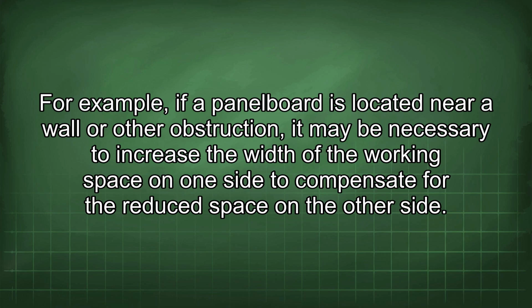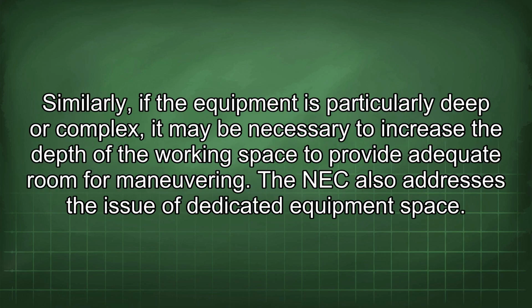For example, if a panel board is located near a wall or other obstruction, it may be necessary to increase the width of the working space on one side to compensate for the reduced space on the other side. Similarly, if the equipment is particularly deep or complex, it may be necessary to increase the depth of the working space to provide adequate room for maneuvering.